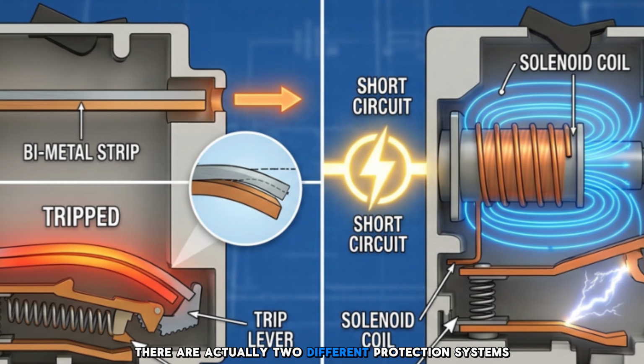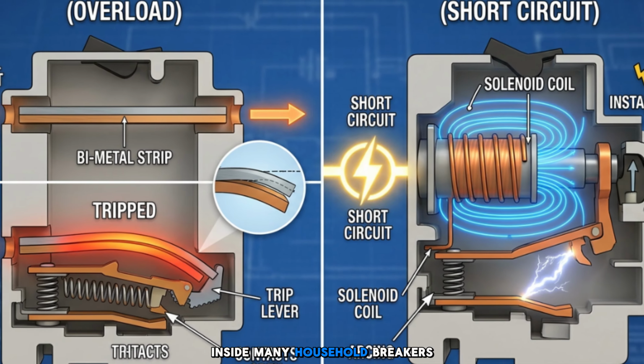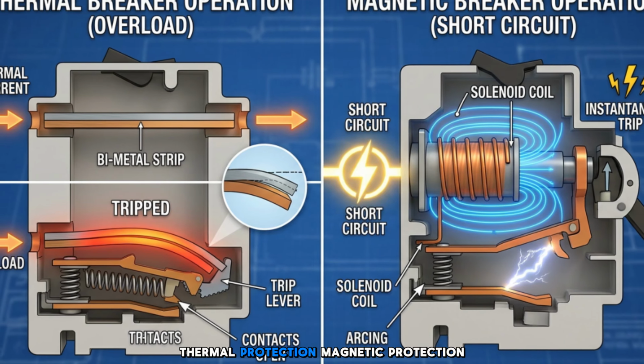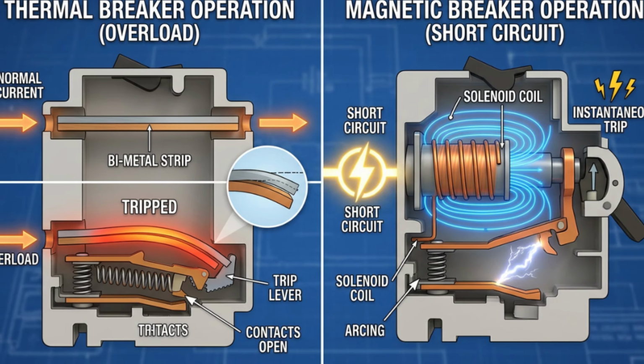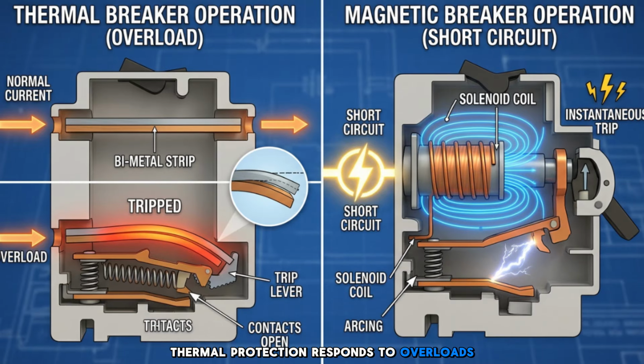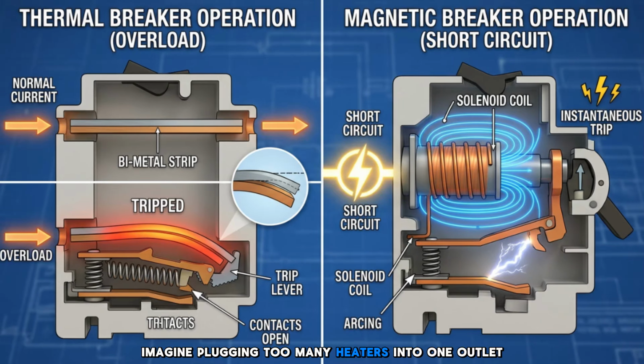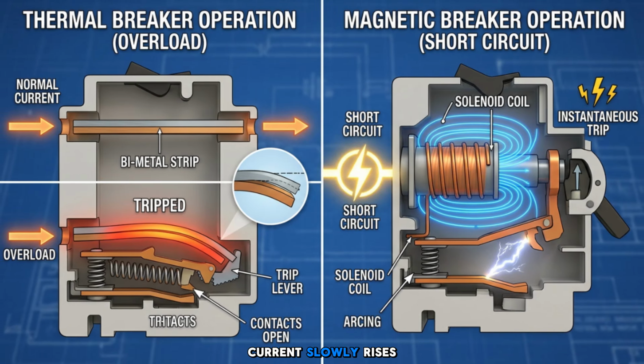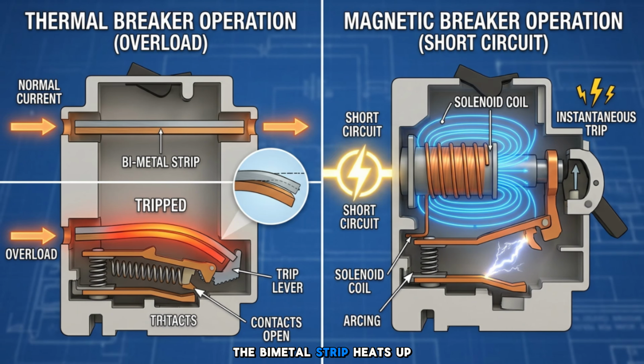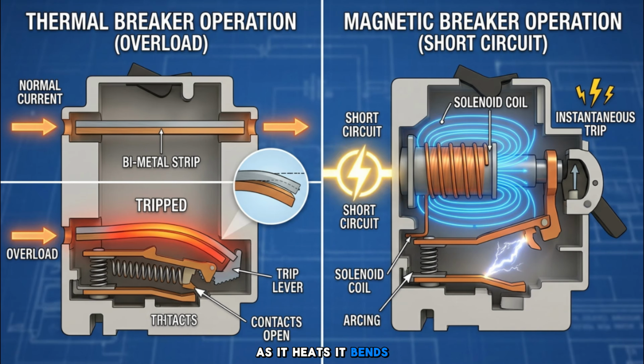There are actually two different protection systems inside many household breakers: thermal protection and magnetic protection. Thermal protection responds to overloads. Imagine plugging too many heaters into one outlet. Current slowly rises. The bimetal strip heats up. As it heats, it bends. Eventually, it pushes the trip mechanism.